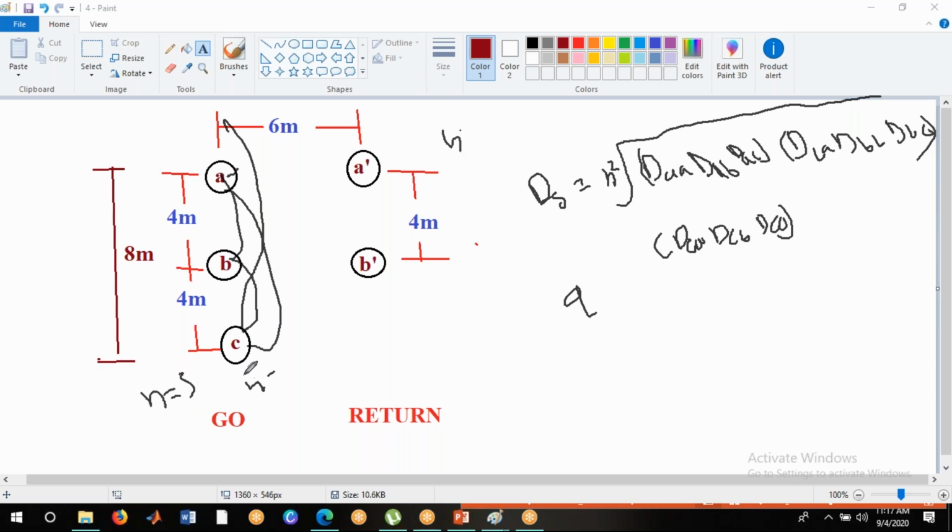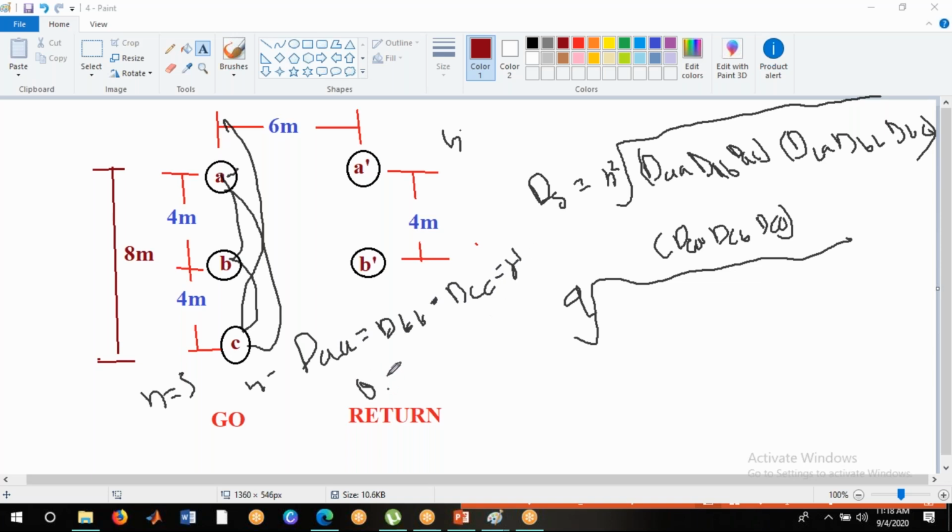So within the conductor we have to find the distance between all the strands in the single conductor. Now, in the 9th root, the self distances DAA, DBB and DCC are equal to R dash. So R dash is given by 0.7788 times the radius.